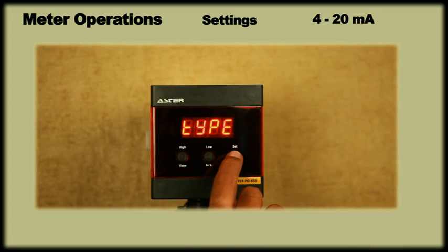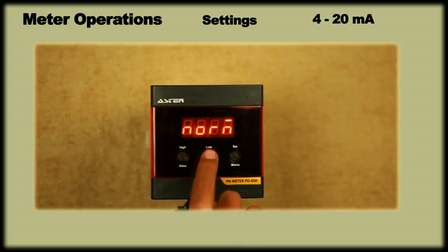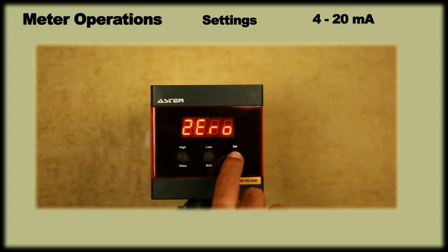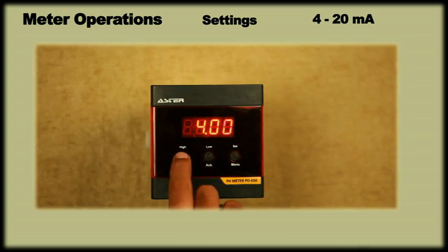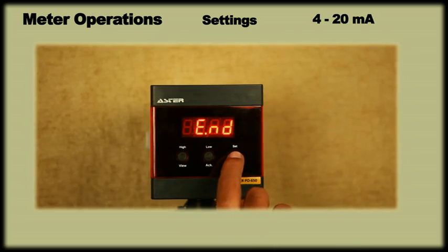On pressing menu, display will show type. On pressing menu again, we can choose the type as either normal that is 4 to 20 or inverse that is 20 to 4 using the ACK key. Then press menu to save and set the 0 value. After setting the 0 value, press menu twice to set the span value. Having changed the span value, press menu twice to end and save the setting.